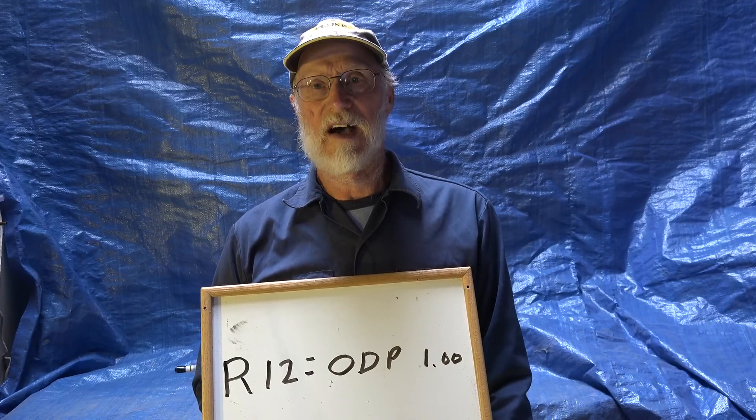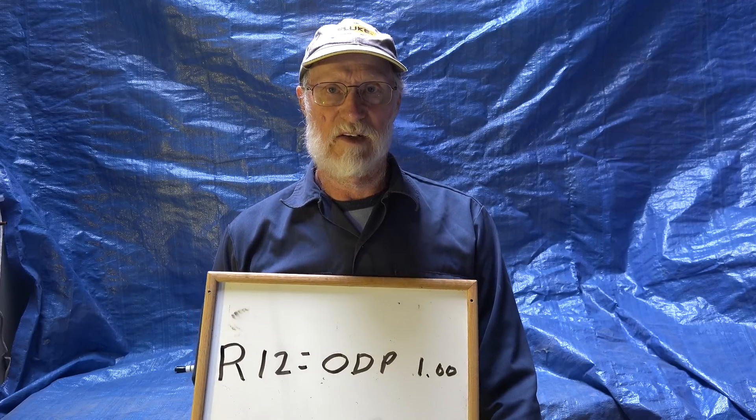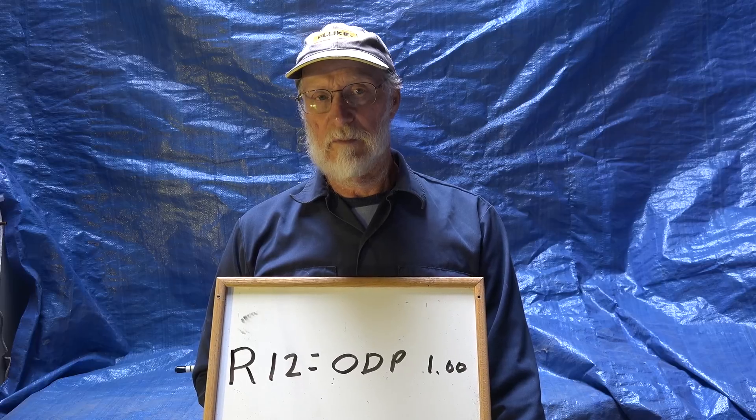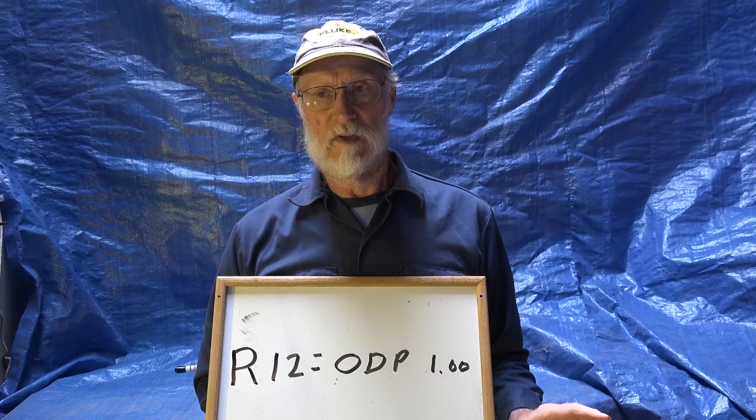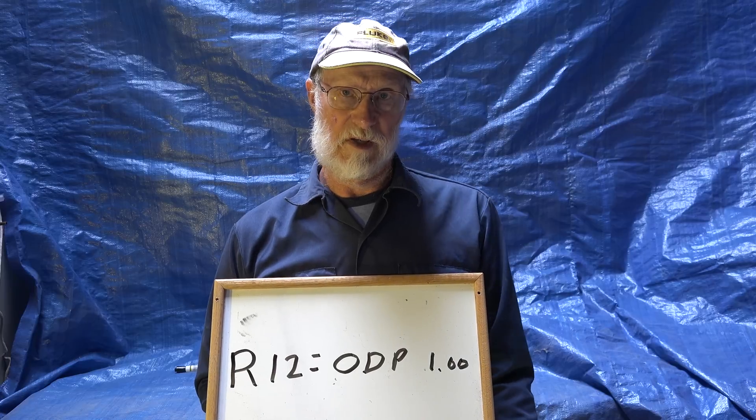R12 has an ozone depletion potential of one — that's the highest; everything else is a percentage of one. So because it was one of the worst refrigerants for ozone depletion, we stopped using it. I think around 1992 we stopped using it. There were some replacements for it, which I'll go into later, but ozone depletion potential was the reason we started changing refrigerants, and especially why we stopped using R12.